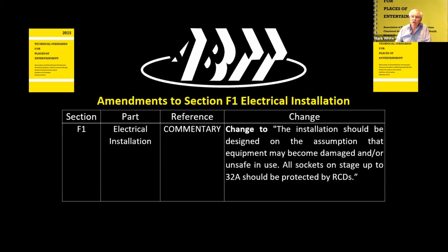So what we say is that, yes, indeed, you do have to have RCDs on each circuit. It's each final circuit. While we may use 32 amps as a distribution unit fed off in the usual way of what we call the temporary power, 7909 makes an emphasis on using 30 milliamp RCDs on each final circuit. So whilst it may be that the 32 amp outlet on your stage is protected by an RCD, it may not necessarily be so, and you are relying on the final circuits. Otherwise, plug in 6 or more LEDs into your one circuit, each of which is drawing, say, 140 watts, and suddenly you discover that your big 32 amp supply goes off because of this phenomenon of earth leakage.